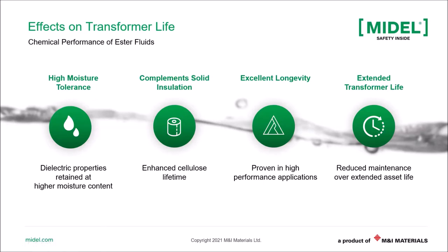So even though ester liquids can hold more moisture than mineral oil, it can retain the dielectric breakdown strength at the higher moisture content. So this is critical because one of the properties that Anthony showed you earlier is that the moisture quantity in ester liquids is higher. So we always get the question from the end user, why is it that if the moisture is higher in ester liquids, they can still retain the breakdown strength? And that has to do with just the chemical nature of the dielectric liquid. It holds the moisture at a stronger bond, hence it allows for the dielectric breakdown properties to also be retained.